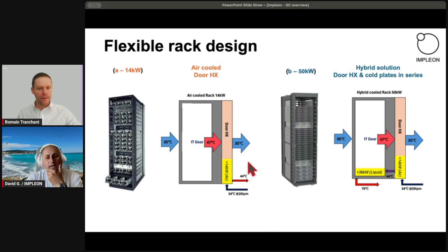Yes, so exactly on this slide, you see that in air cooling, we can have 34 degrees inlet water, 44 outlet, regarding the OCP servers, they can work with 35 degrees ambient air. But when we shift to on-chip cooling, we can have 34 degrees inlet water for the rear door heat exchanger, after that 44 outlet. And with on-chip cooling, we can achieve up to 70 degrees outlet hot water.